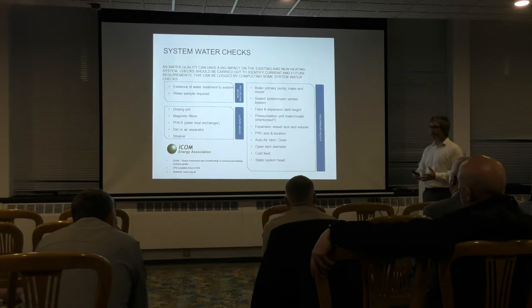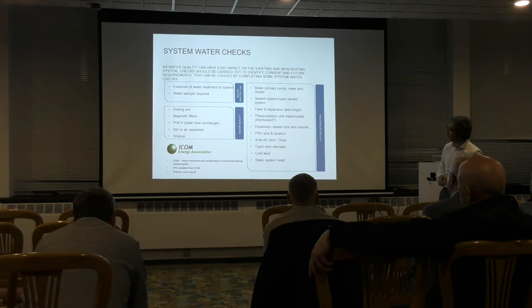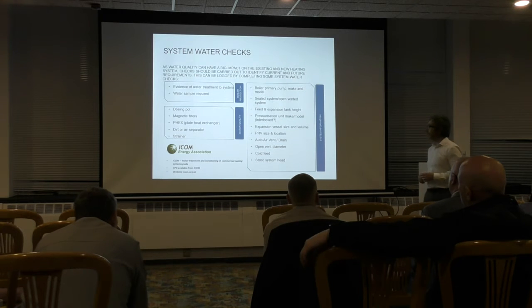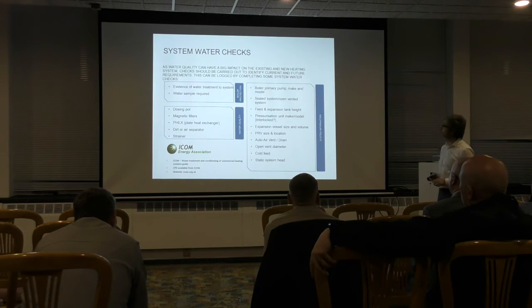You've got your boilers sitting there. They're on their own little primary system with their plate heat exchanger, and then beyond that, on the secondary side, well, if it's an old, dirty old system, then we'll find it doesn't matter. Your boilers are protected by the plate heat exchanger. Air dirt separators as well, and also strainers. Very standard practice, I suppose, to put those type of things in.